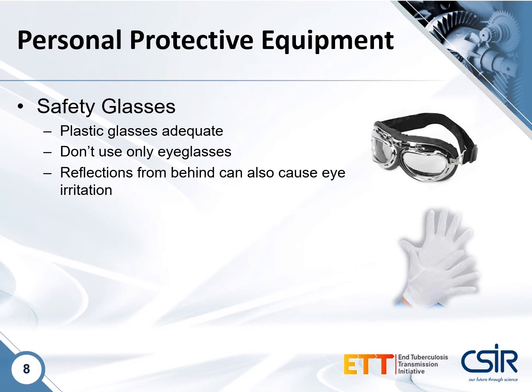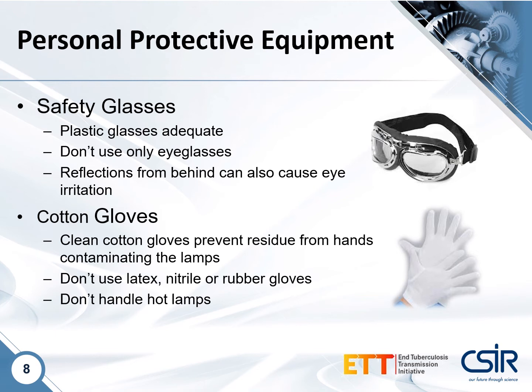So if you have to wear your own eyeglasses while you're doing work in the upper room, just make sure that you have goggles over your eyeglasses as well. And then to protect the device from contamination from your hands, you need to use cotton gloves. Clean cotton gloves prevent the residue from your hands from contaminating the lamps and thus reducing the output of the lamps. Don't use latex gloves or nitrile gloves or rubber gloves, as these can also leave deposits on the lamps, especially if the lamps are hot, and as a rule, don't handle hot lamps.